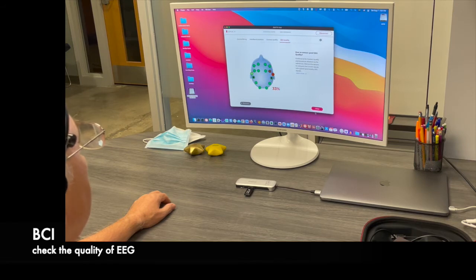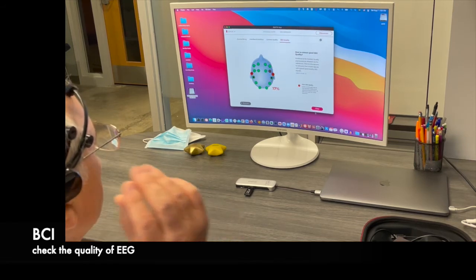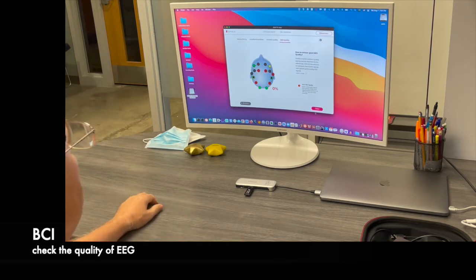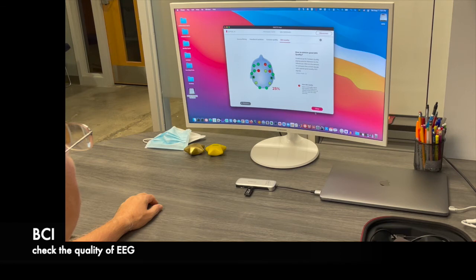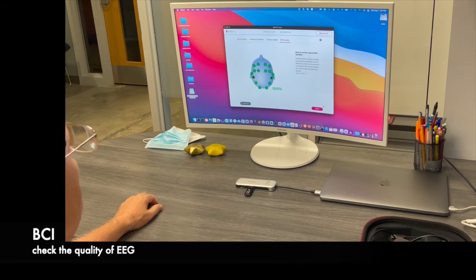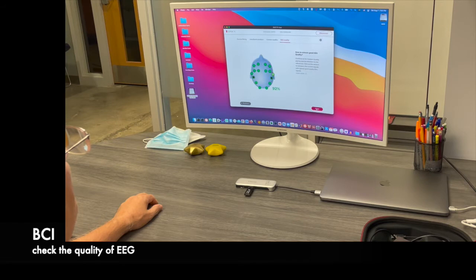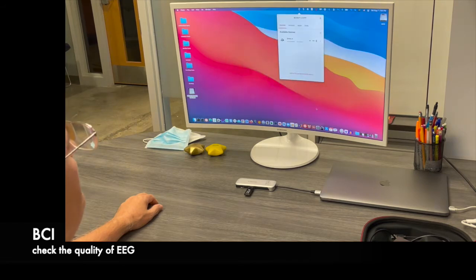So you'll have to maintain a very good electric contact. And that's where you can use a little bit more saline, have a colleague helping you out. So what you want is the signal to be over 90 percent in the range of 100 percent. And you'll always notice which electrode is going off.